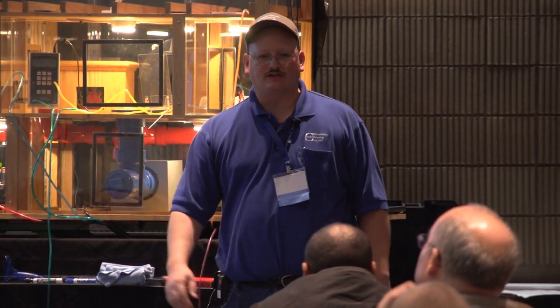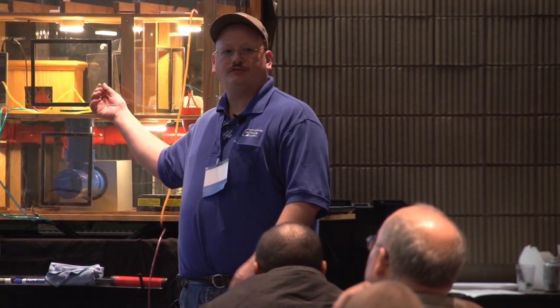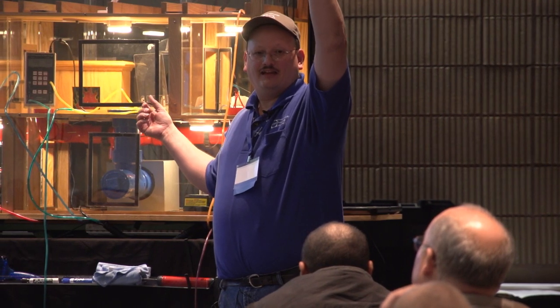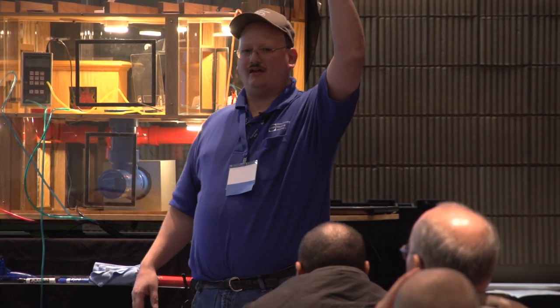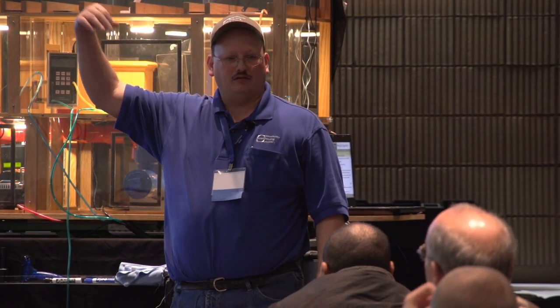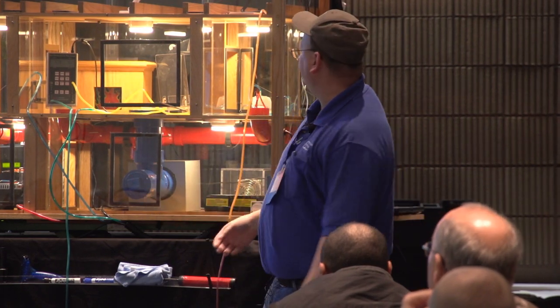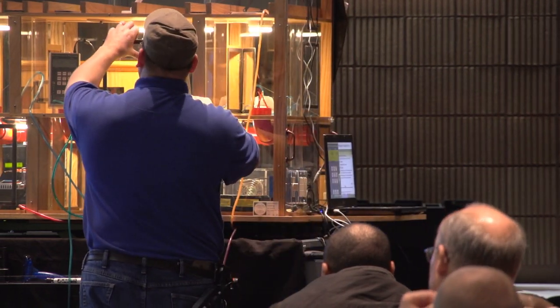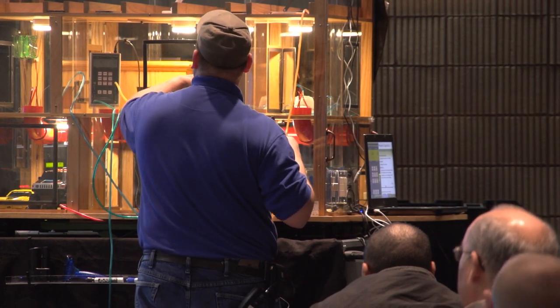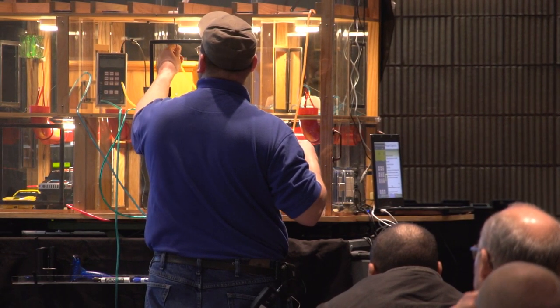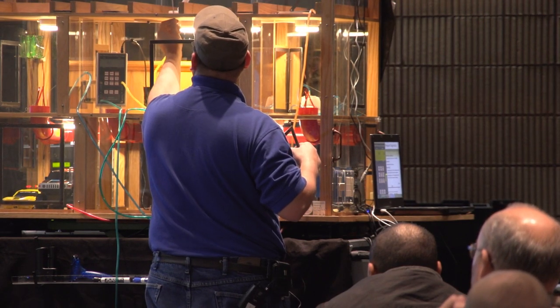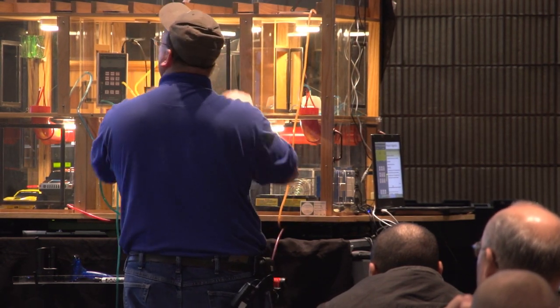So what about the attic? How would I do a zonal test in the attic? What would I do? So I take this yellow hose, put it in the attic? Yeah. And how do you guys normally do that? Sometimes you might drill a hole. Anybody ever put a hose in the attic before you run the blower door and then close a hatch on it, so you've got one hanging down? Sometimes you can do that. So all I'm going to do is take this out and put it in the attic right here. It's going to stick up in the attic.